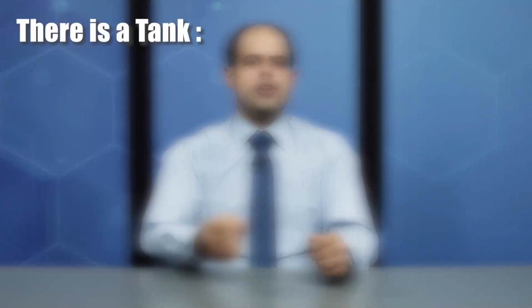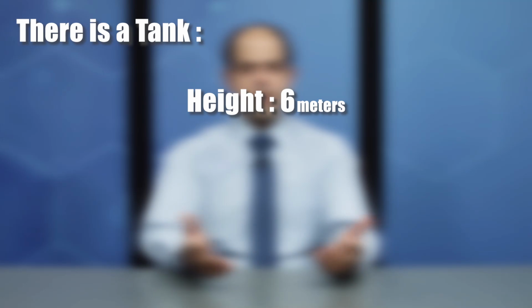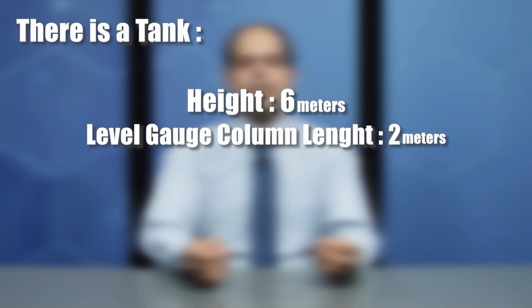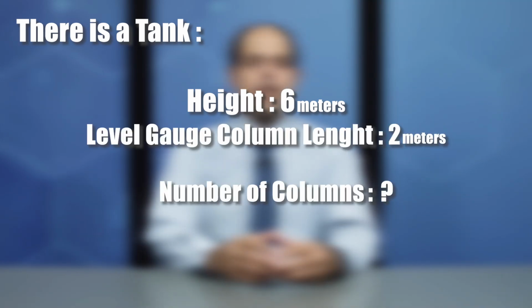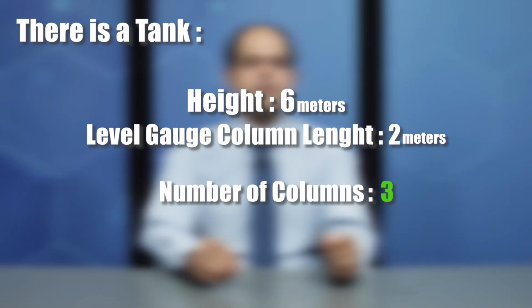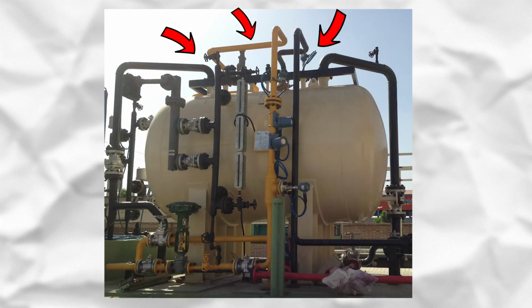For sure, the length of this column has limitations and you are not able to design it in longer dimensions. Just imagine there is a tank with a height of 6 meters and the length of the level gauge column is just 2 meters. It is clear that you need 3 columns to measure the height of the tank. In this regard, we consider a pipe called a standpipe on the tank. Then those 3 level gauges are installed on this standpipe. Undoubtedly, the overlap between columns must be considered.